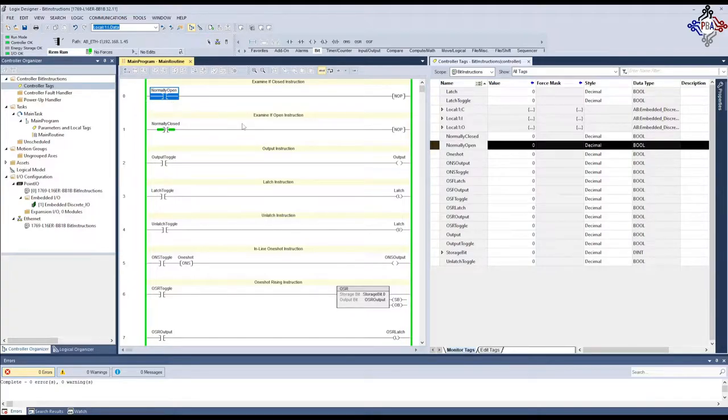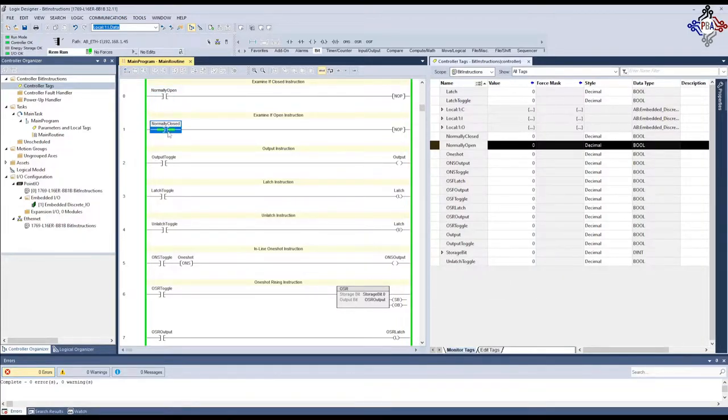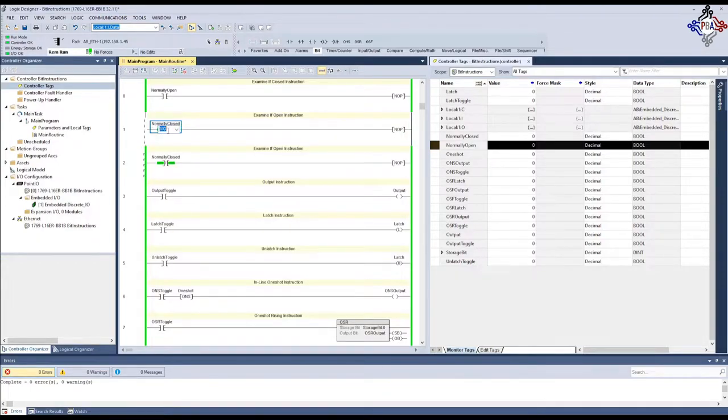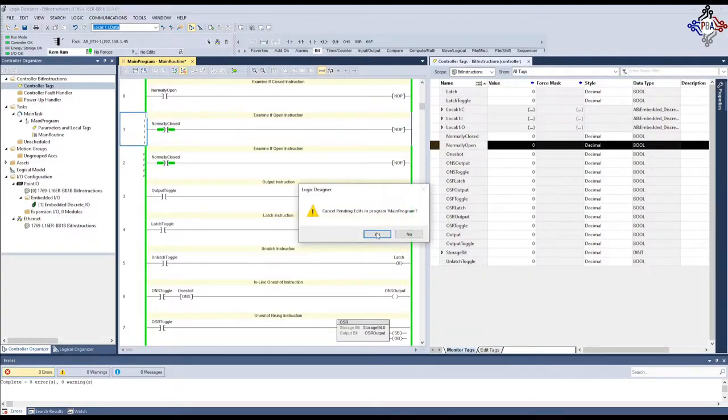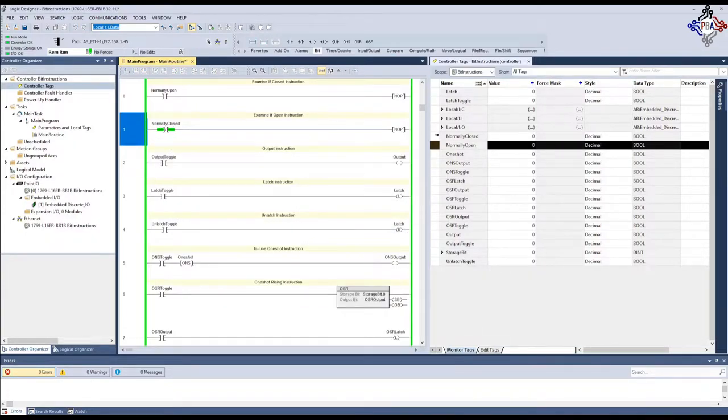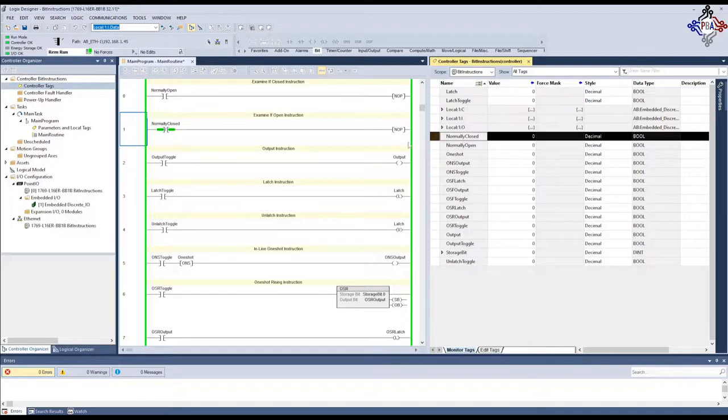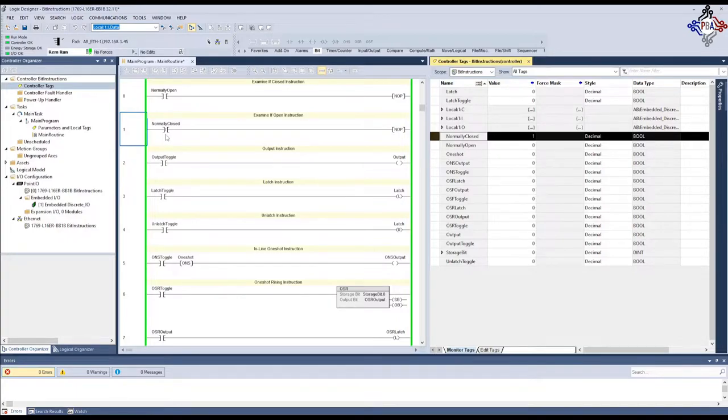Now, moving on to our normally closed, or the XIO, examine if open instruction. This one is tied into this tag, or normally closed tag. You see that this one is lit up green. It's actually examining right now because our tag is off. If I come over here, again, Ctrl T to toggle. I toggle that on. You see that the instruction stops scanning. It stops examining that instruction. If I turn it off, it begins examining it again.